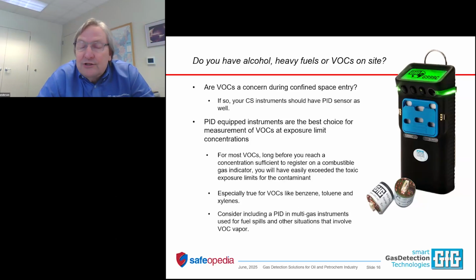If you have the presence of alcohols, heavy fuels, volatile organic chemicals, you're going to need a fifth sensor, and that's generally a photoionization detector sensor or a PID sensor. PID-equipped instruments are by far the best choice for the measurement of VOCs at exposure limit concentrations. For most VOCs, long before you reach a concentration sufficient to register on a combustible gas sensor, you will have already exceeded the toxic exposure limit for the contaminant. This is especially true for VOCs such as benzene, toluene, xylenes, phenol, cumene. So consider including a PID in any multi-gas instruments used for fuel spills or other situations that involve VOC vapor.